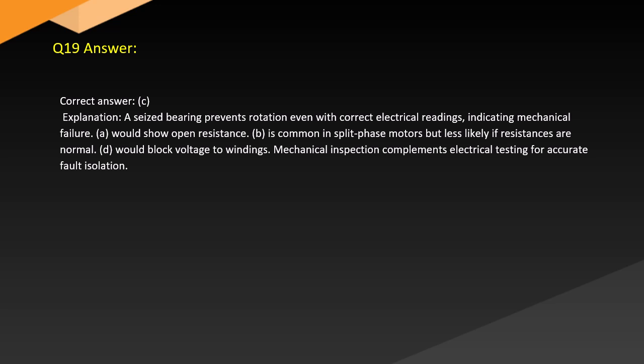Answer. Correct answer: C. Explanation: A seized bearing prevents rotation even with correct electrical readings, indicating mechanical failure. A. Would show open resistance. B. Is common in split-phase motors, but less likely if resistances are normal. D. Would block voltage to windings. Mechanical inspection complements electrical testing for accurate fault isolation.